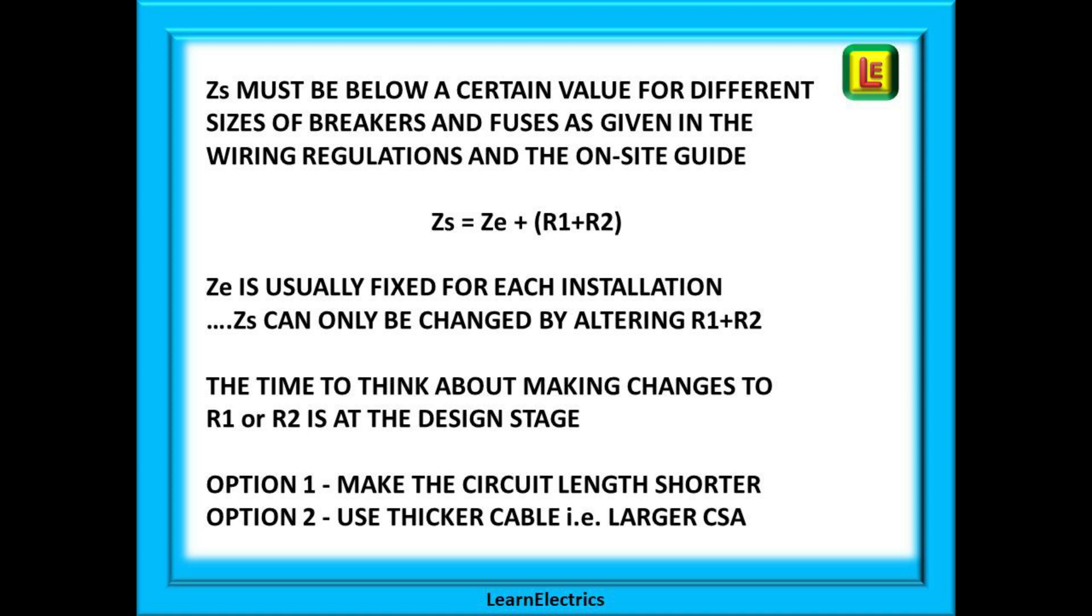We showed earlier that ZS equals ZE plus R1 plus R2. ZS is the resistance or impedance of the whole wiring system including the outside of the building and the circuit inside the building. In other words, the whole thing. ZE though is the external values and these are generally fixed for each building. It will not change. This means that ZS can only be changed by altering the value of R1 plus R2. In other words, we can only make ZS fall into line with the regulations by making changes to the internal wiring, our R1 plus R2.